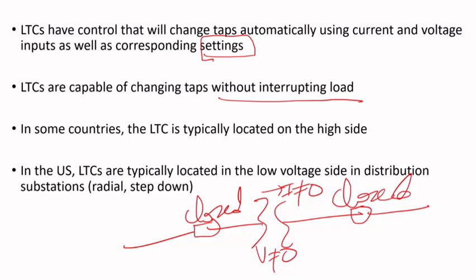There will be no damage, as the tap changer is designed for that purpose. In some countries, the LTC is located on the high side, but in the United States, LTCs are typically located on the low voltage side — for instance in distribution, for radial or step-down applications where you step down from high voltage to low voltage. There are cases where it might be on the high side as well.